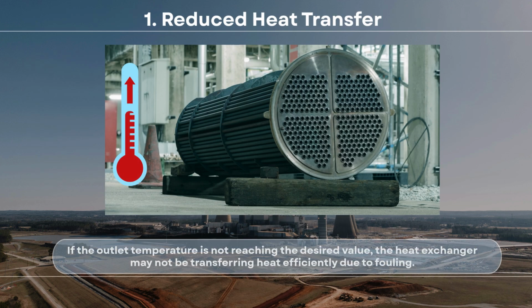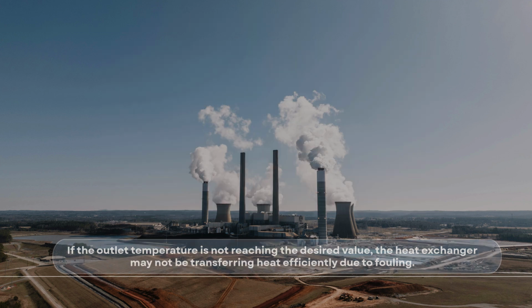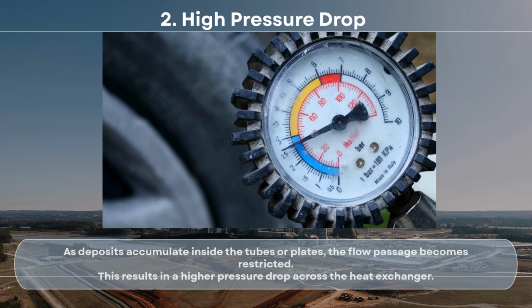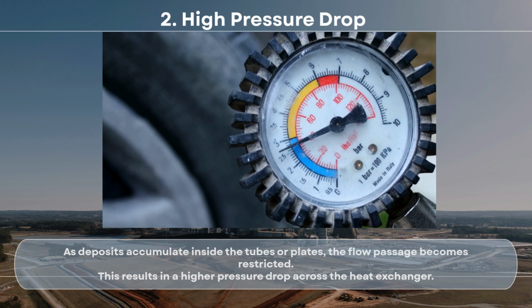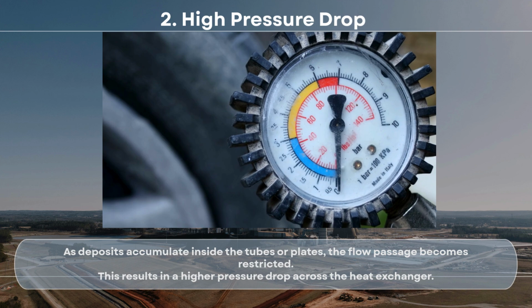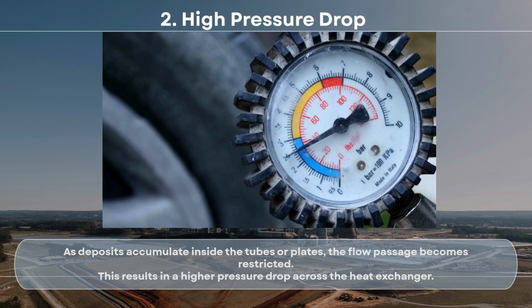If the outlet temperature is not reaching the desired value, the heat exchanger may not be transferring heat efficiently due to fouling. Number 2. High pressure drop. As deposit accumulates inside the tubes or plates, the flow passage becomes restricted. This results in a higher pressure drop across the heat exchanger.